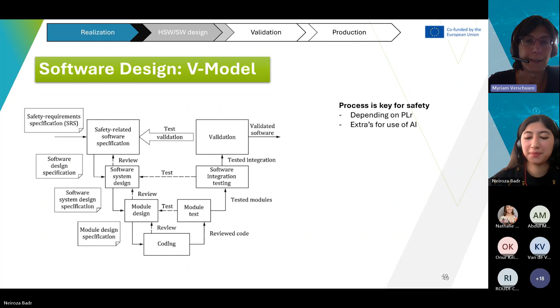So for the software implementation, you have your safety related software. Be aware not to mix safety related functions with non-safety related functions. What do you have in your safety related software? Typically monitoring, to make sure you have your diagnostic coverage. If you do it by software, you will be doing monitoring here. Also how to reach a certain safe state, which could be done by software. These are examples of your safety related software, like making sure you do not restart unintentionally or stop as you should be stopping, etc. This is your safety related software.